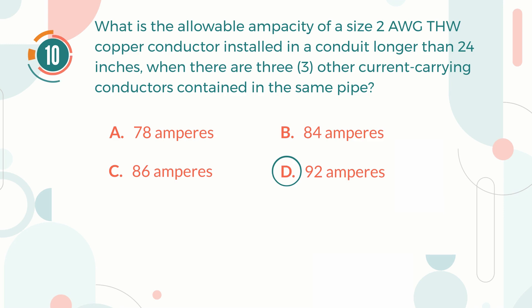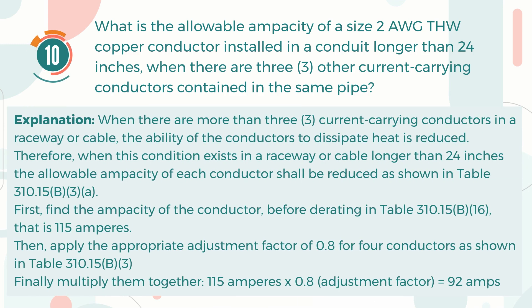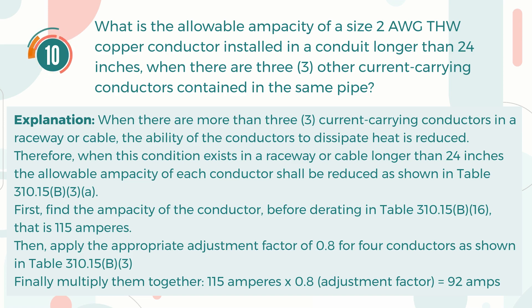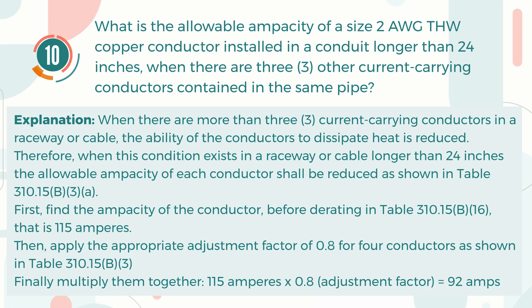The correct answer is D. 92 A. Explanation: When there are more than three current-carrying conductors in a raceway or cable, the ability of the conductors to dissipate heat is reduced. Therefore, when this condition exists in a raceway or cable longer than 24 inches, the allowable ampacity of each conductor shall be reduced per Table 310.15(B)(3)(a). First, find the ampacity of the conductor before derating, as shown in Table 310.15(B)(16), which is 115 A. Then, apply the appropriate adjustment factor of 0.8 for four conductors as shown in Table 310.15(B)(3)(a). Finally, multiply them together to get the answer of 92 A.